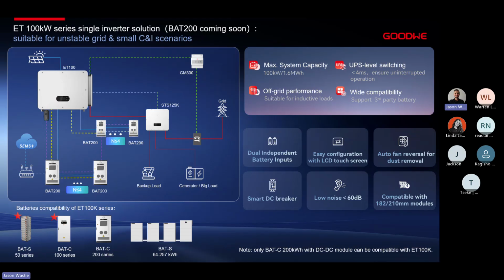Next is the ET100 battery inverter, connecting with our BAT 200, which is a new 200 kilowatt hour battery stack that will be coming soon. The ET100 works very similarly to the ET50, however, it is obviously a much bigger inverter. A few key feature differences: we have 200% PV input oversizing, so 200 kilowatt peak of PV on the 100 kilowatt inverter. We have three different models of STS that we can connect to. The standalone STS being the 125 kilowatt STS, and then a 350 as well as a 700 kilowatt STS that we'll connect to. How this will work, I'll get to in a few slides' time.